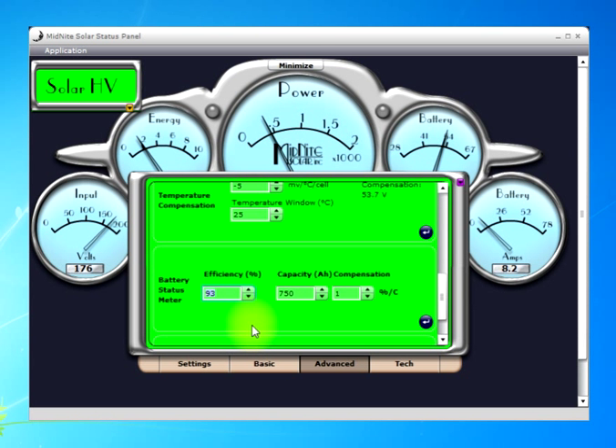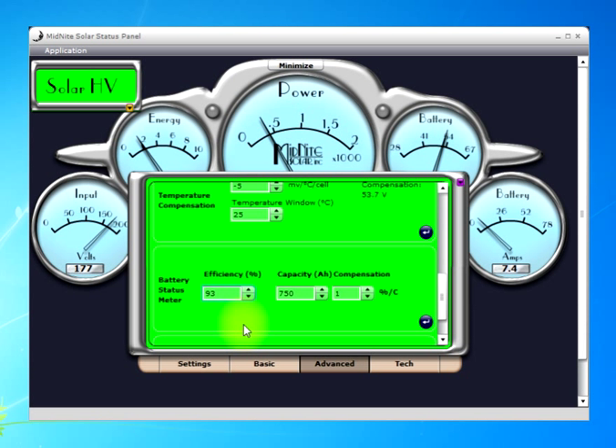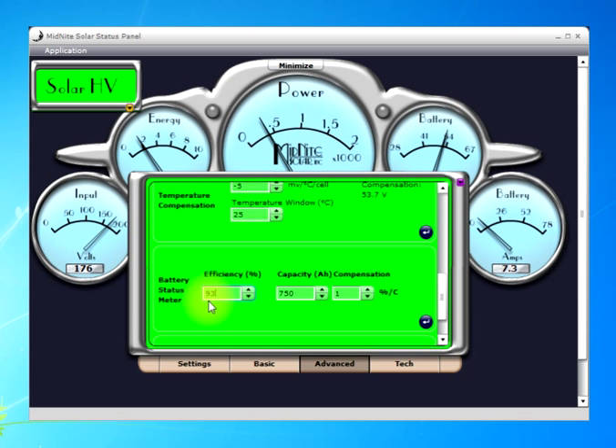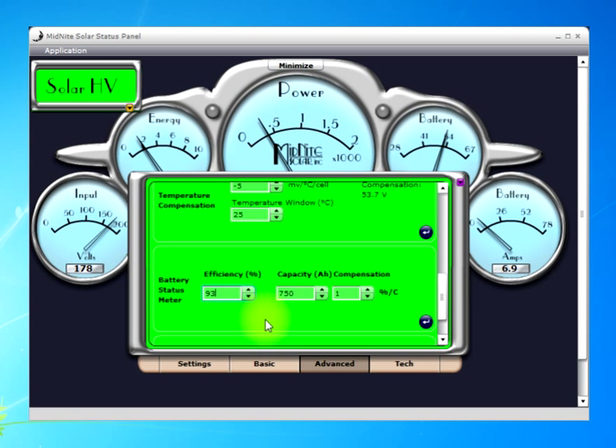I've found that on my particular bank of Trojan L16REBs, about a year old, 93% efficiency gets me right about where I want to be. What you're looking for is: as the controller goes through its absorb cycle, the state of charge should hit 100% at almost exactly the same time the controller goes to float. If it's hitting 100% 30 minutes early, the efficiency number is probably too high. If it only reaches 90% when it goes to float, the number may be too low. You may need to play with this to tune it in, and you'll need to drop the percentage as the batteries age.